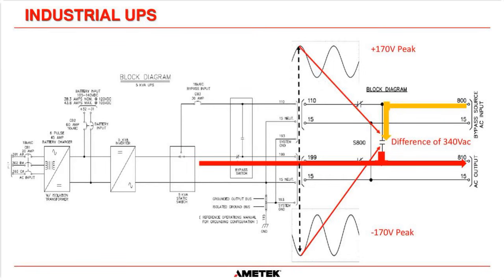So remember, this red line here, this is in normal operation. The inverter is feeding the load, okay? Now let's say this is our bypass supply coming in here, and something has caused the synchronization between the inverter and the bypass to go out of whack for some reason, okay? Let's say they're completely out of phase with each other. So let's follow this hashed line here. At the top here, the bypass is at the top of its peak on the voltage, but at the bottom here, the inverter is on the bottom of the peak of the voltage.